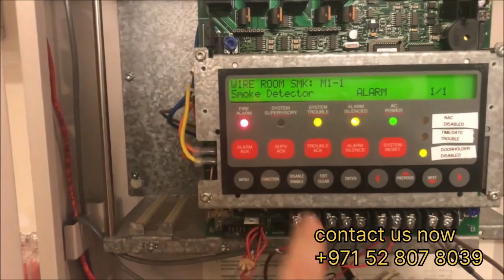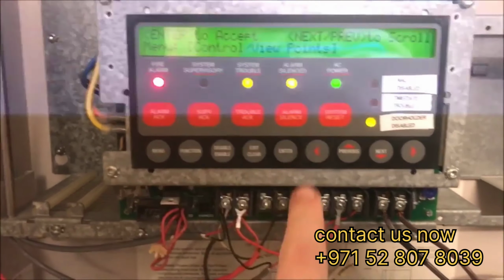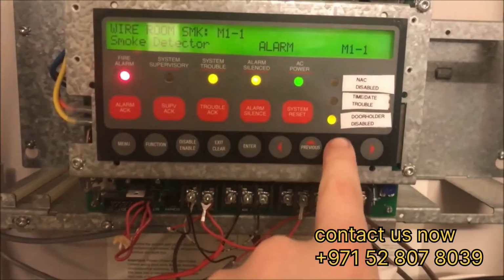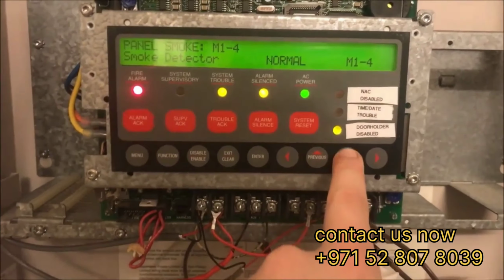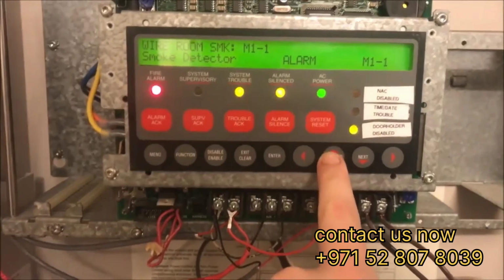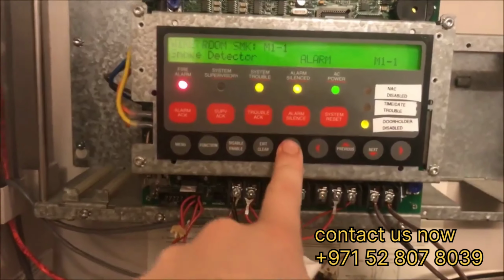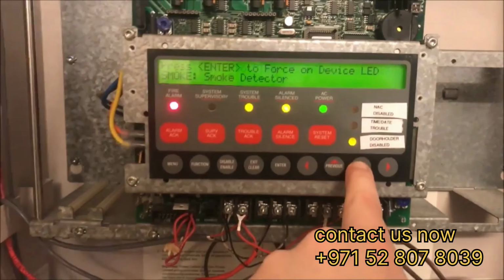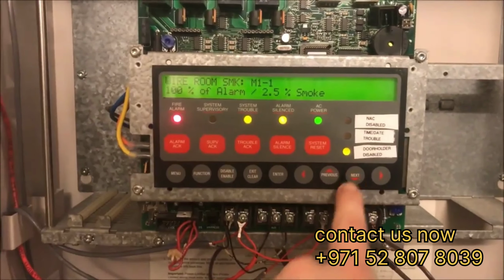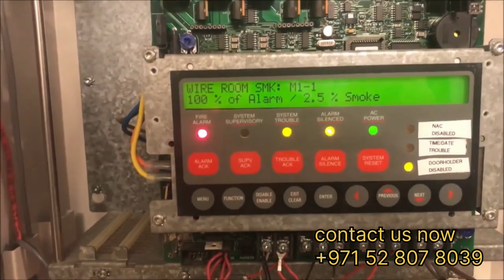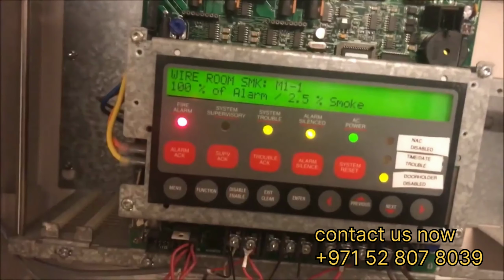Alright, so you can see it's at 100% of alarm. So if we go back, oops, I didn't click it. So if we go into that smoke detector and go down, you can see it is at 2.5% concentration of smoke.